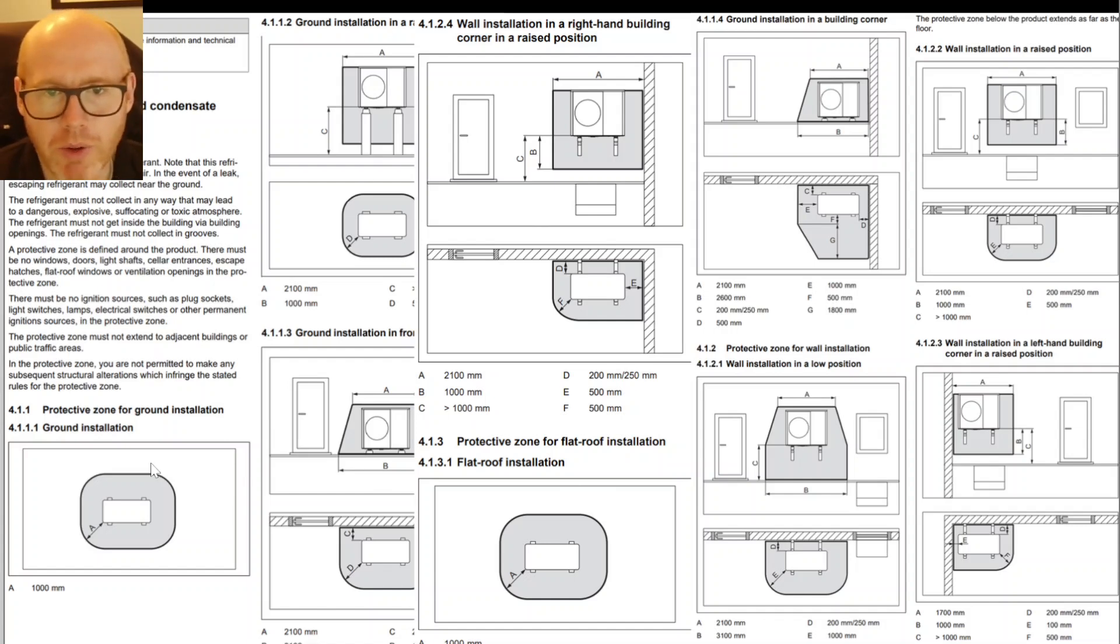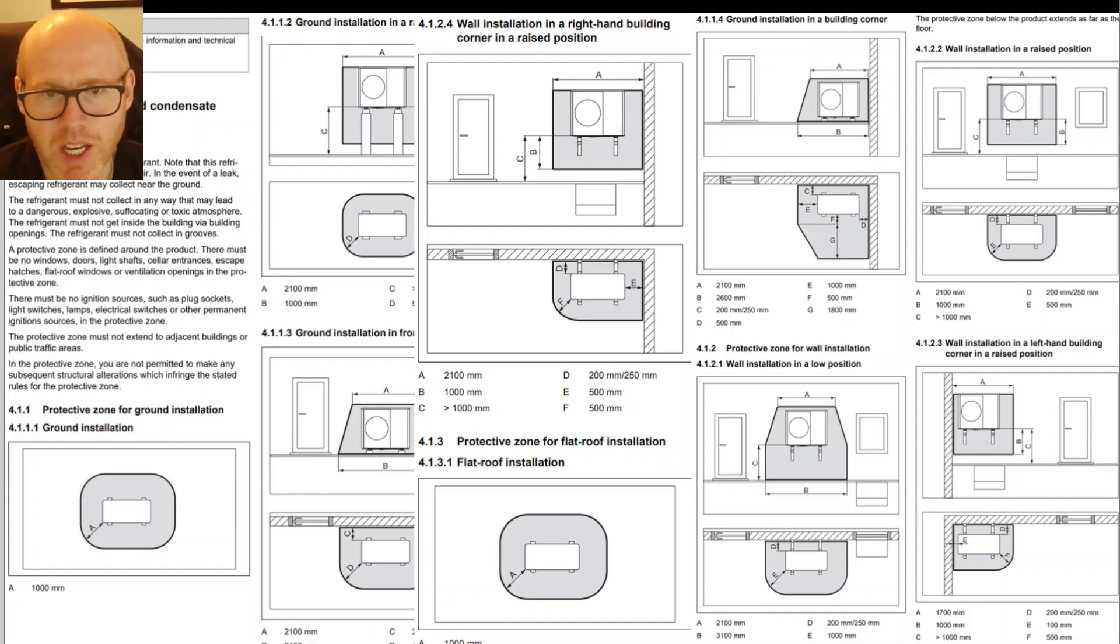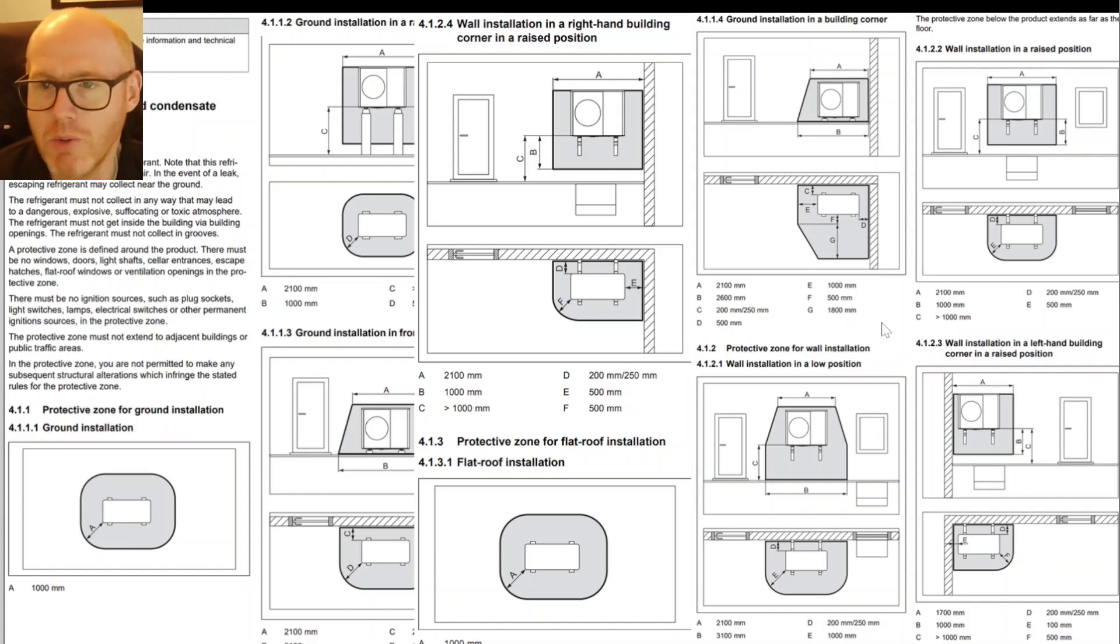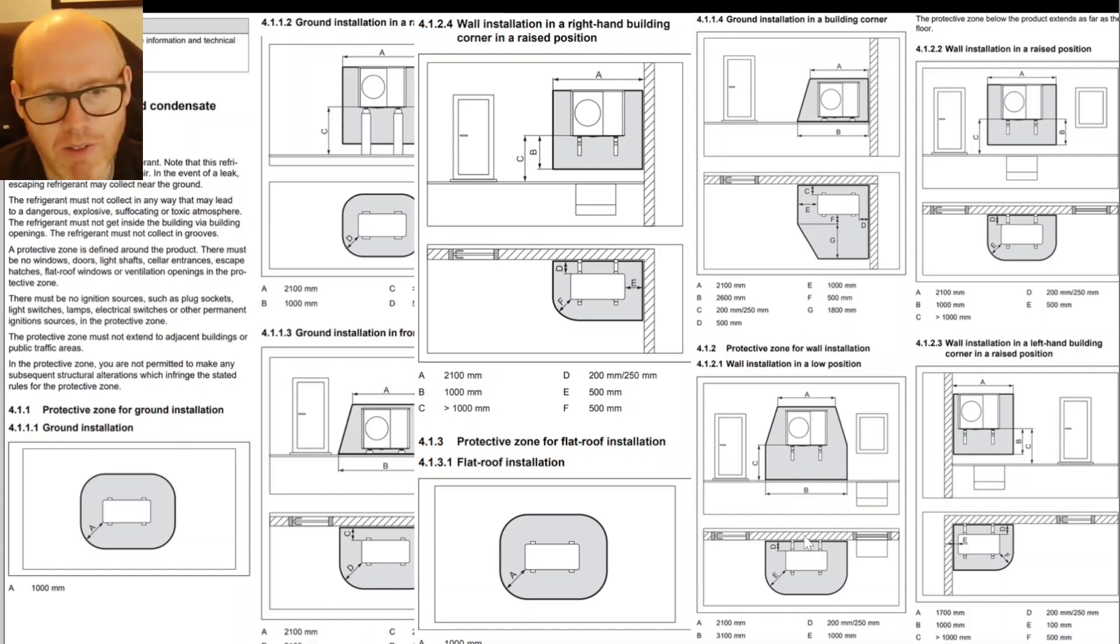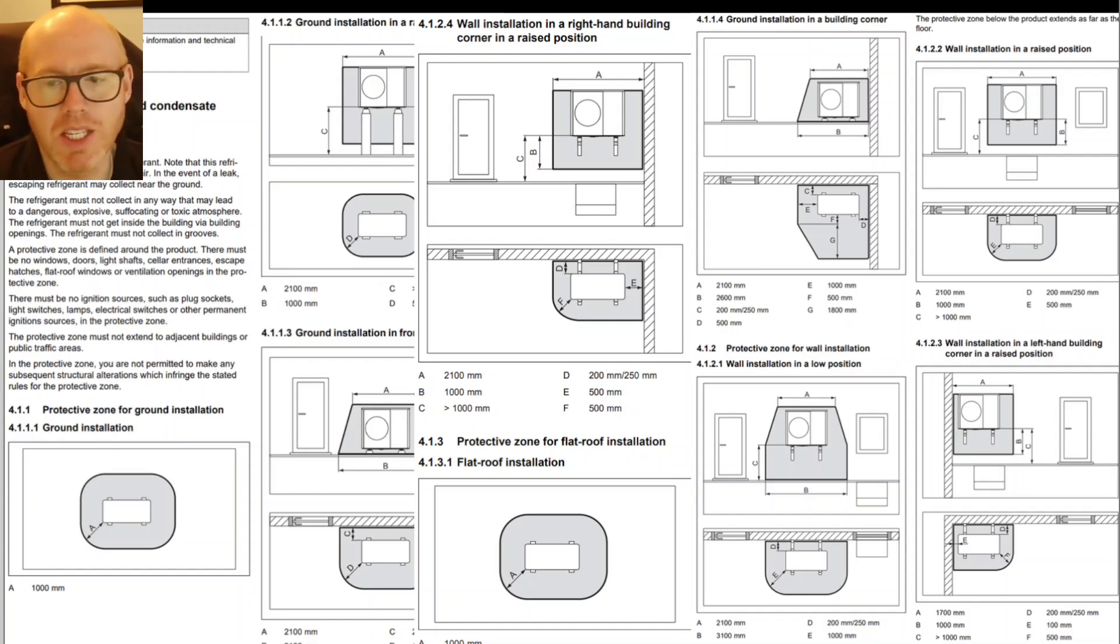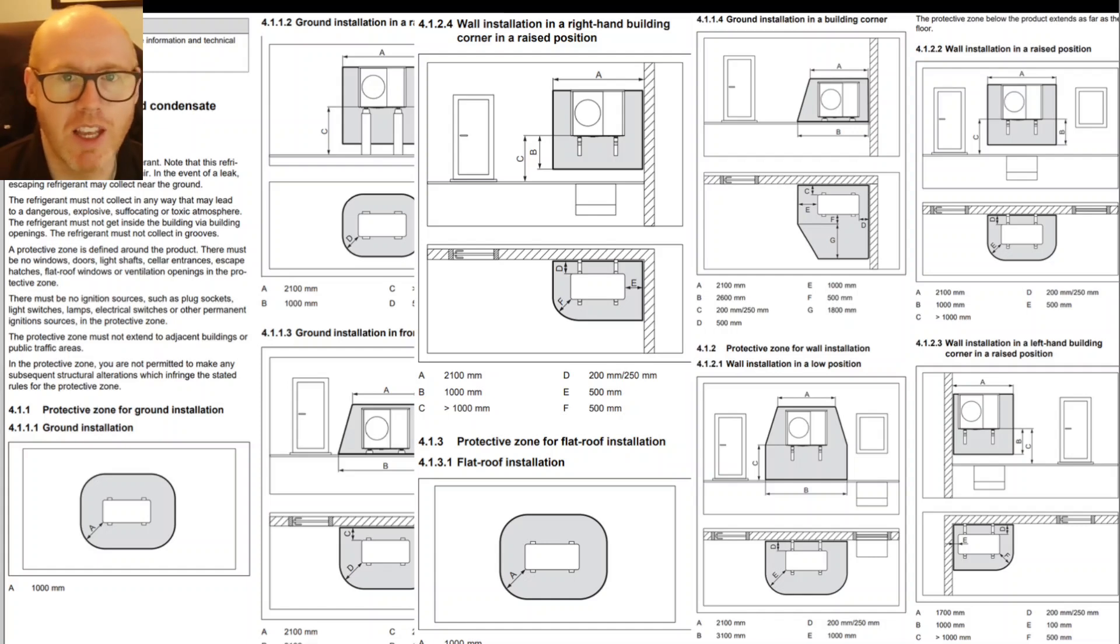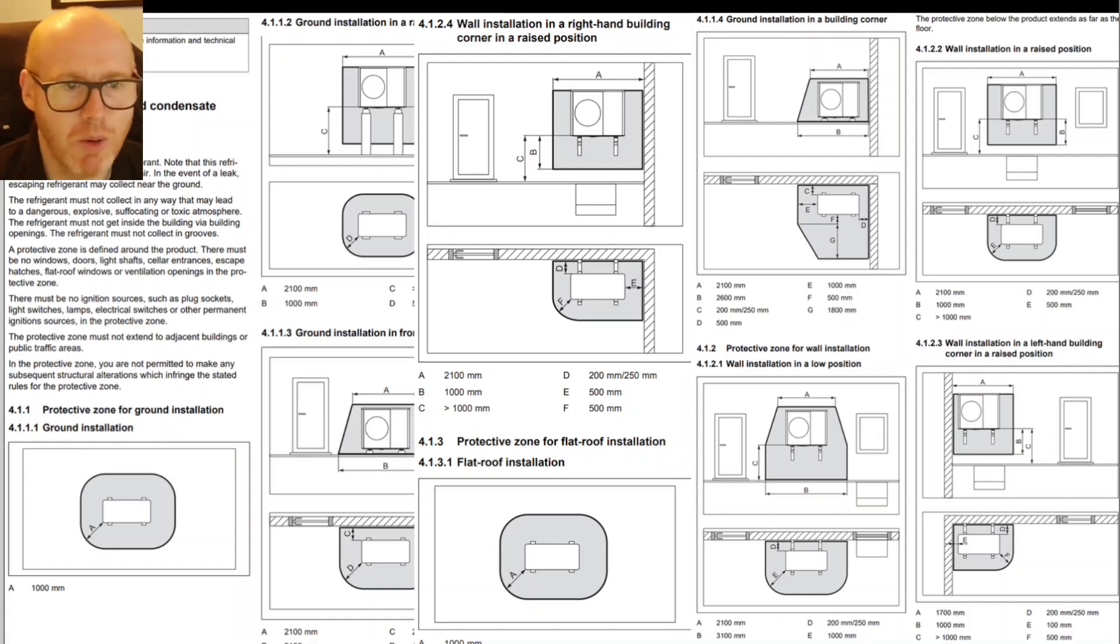For example here if we look at A down in the bottom left hand corner, it's asking us to leave a meter all around the heat pump as a protective zone and you can see the various different installations, you may be able to identify which one yours is. You may have windows, you may have doors, you may have it wall mounted, you may have it floor mounted but they give you all the advice. But what happens especially on smaller properties and the vast majority of the UK is we're trying to keep it one meter away from the boundary because of ridiculous planning restrictions and permitted development rights.